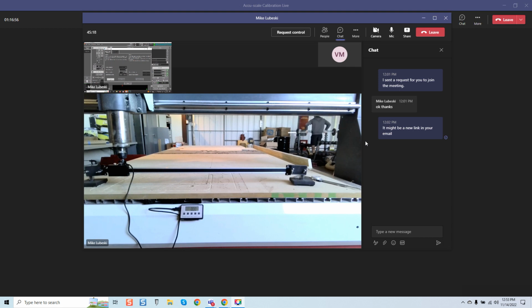It's called the Accu-scale, and what it allows is for end users to calibrate their system at distances exceeding 1 inch. We've typically seen in the industry a limitation of only being able to use a dial indicator, which may be okay for a smaller length machine, but machines in excess of 4 feet, 8 feet, 10 feet, they want an actual calibration that's going to give them a scale percentage that they can work with and really extrapolate out any variances over distance.